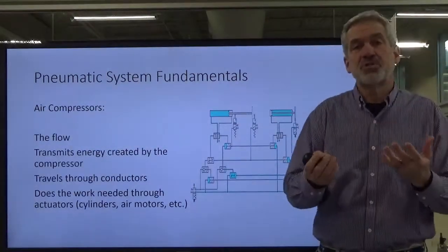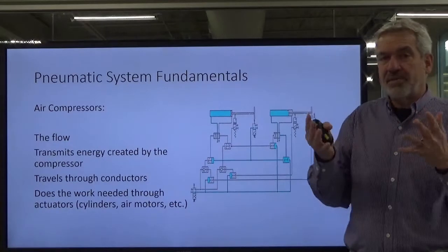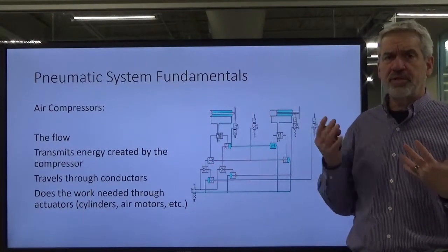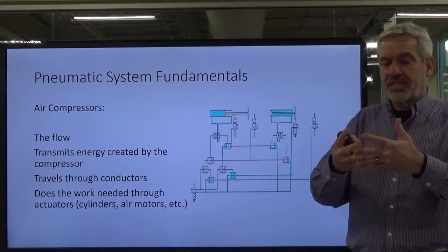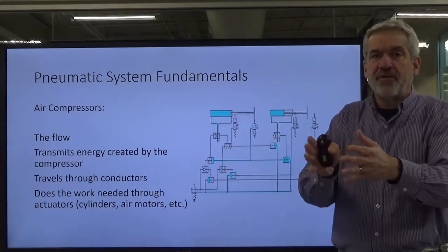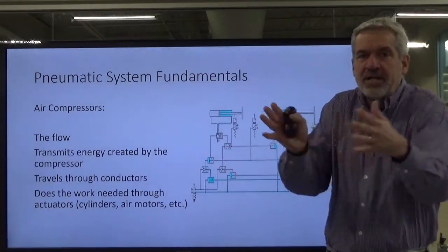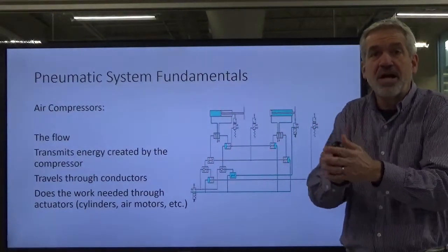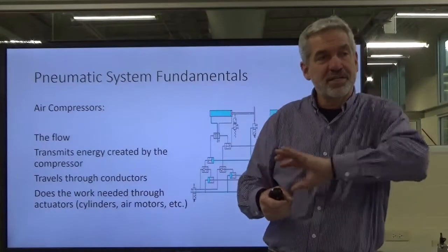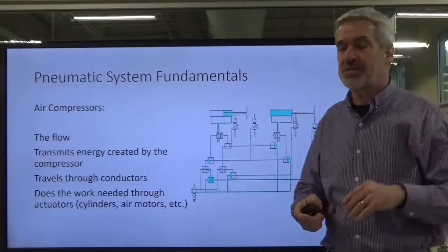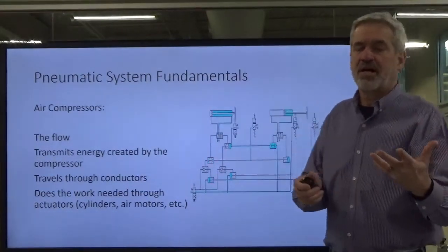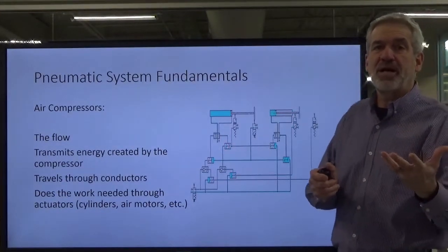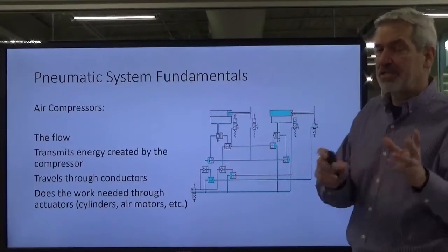Same thing applies with a screw type compressor too. Don't get me wrong, this is not just for the reciprocating. Remember, we said our screws got tighter and tighter, and the volume at which it's packing that air in is decreasing. The volume is getting smaller and smaller, and the pressure is increasing, and it just charges out of the pump into our system. So it works for the screw compressor the same way it does with the reciprocating. Just want to make sure you understood that.